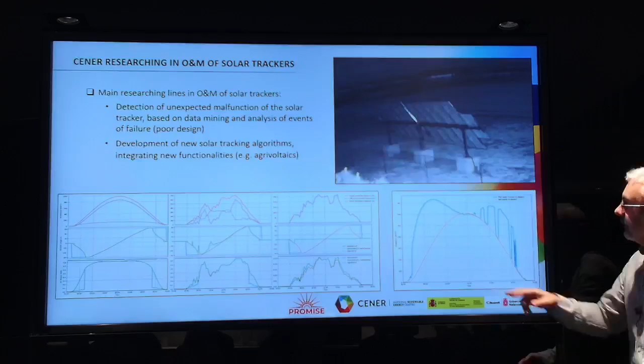Solar trackers: one of the main research lines of operation and maintenance is the detection of unexpected malfunctions of solar trackers based on data analysis of events or failures. In this case, this is the curve of radiation on a horizontal plane, and we expect that the curve on a horizontal single axis presents this shape, but in this case these dips appear, placing the tracker in the horizontal position. This is another malfunction.